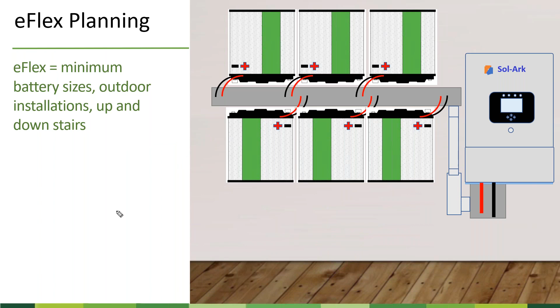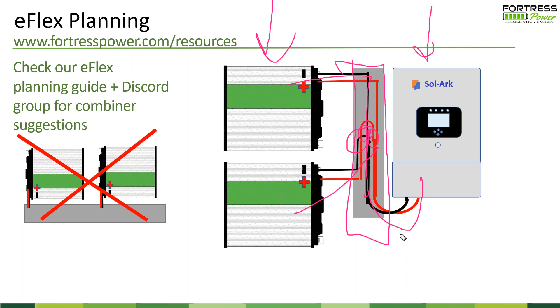There are different ways to get the balance of system material down to a minimum. What's the smallest project you could sell to a customer? You could give them one Sol-Ark with 2 eFlexes, put a trough down the side, run the eFlexes into a combiner point, and run that into the Sol-Ark.